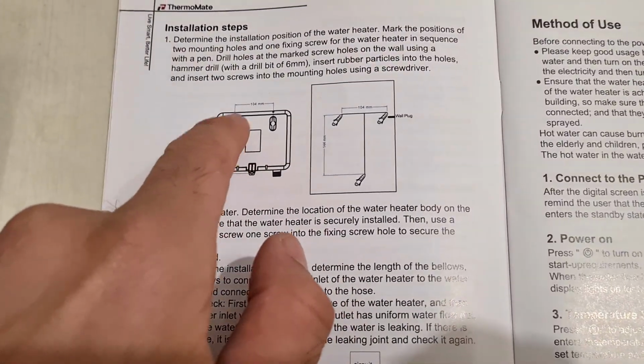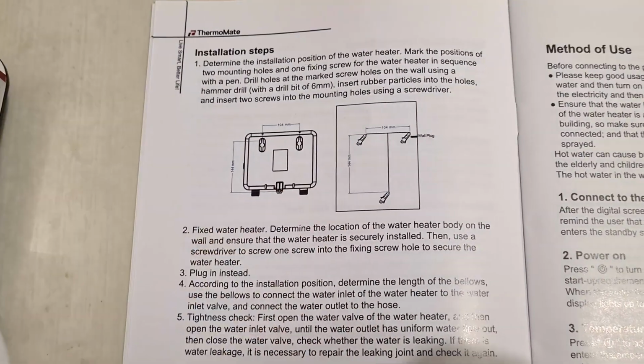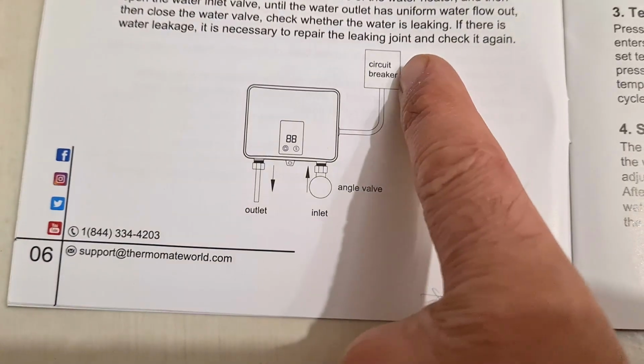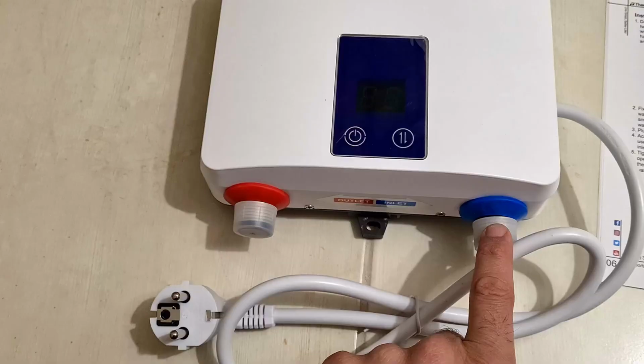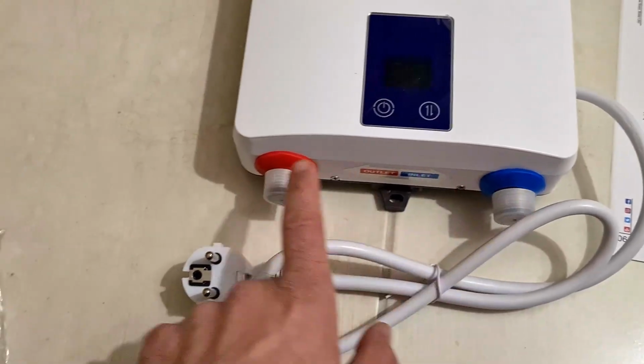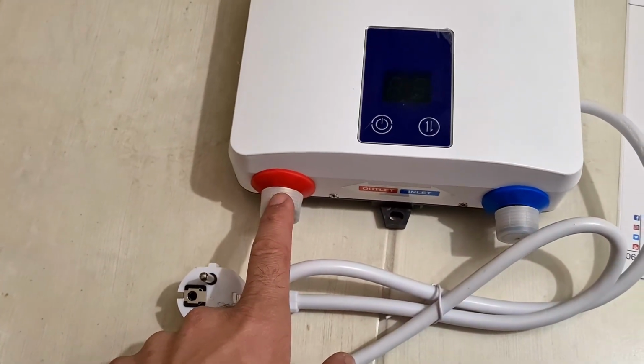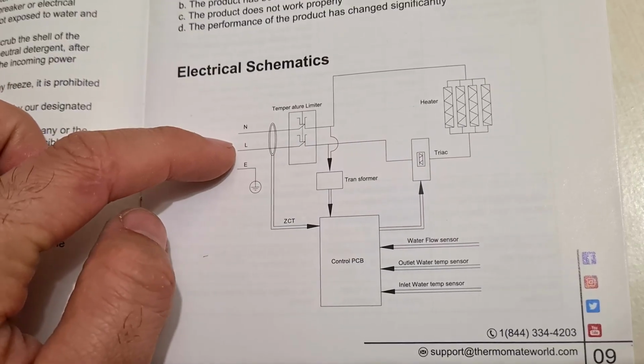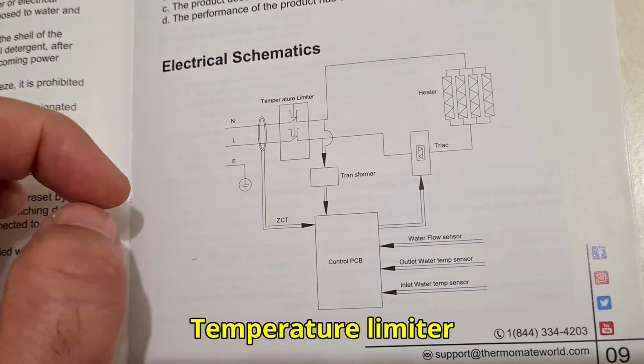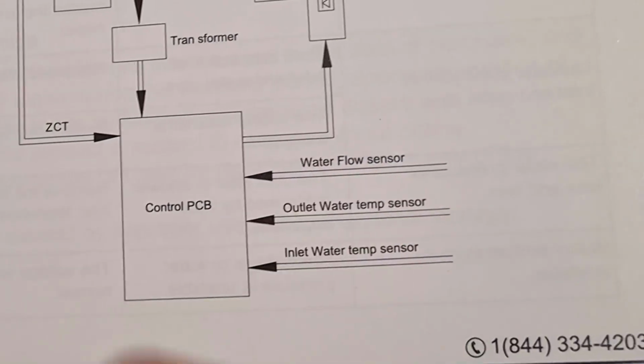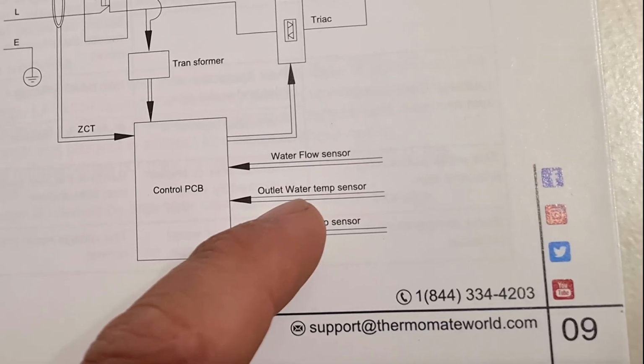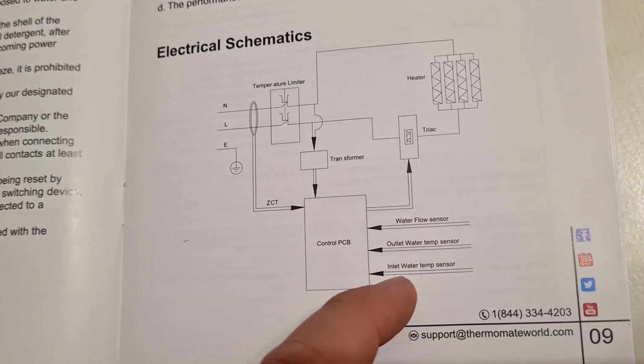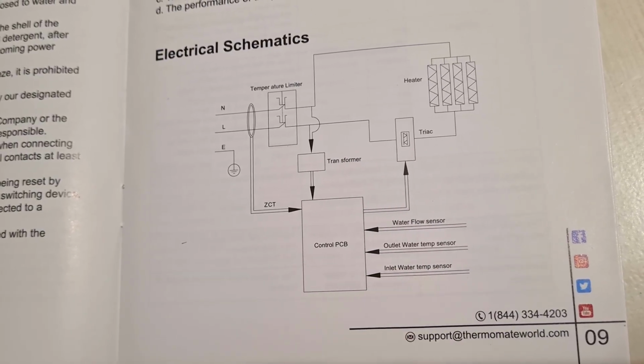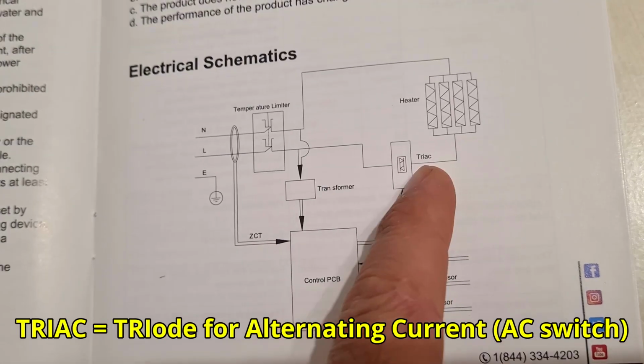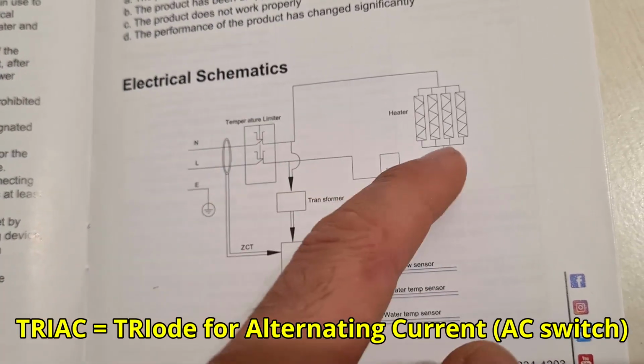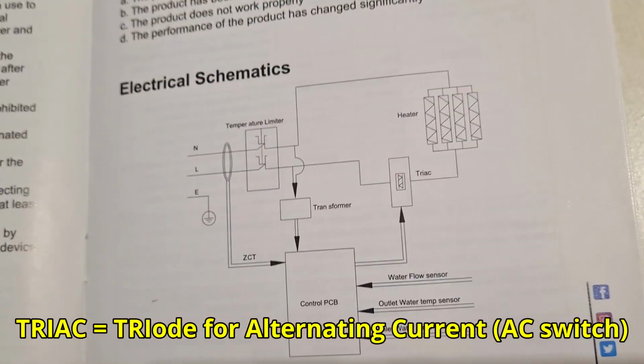That's the back side, 2+1 connectors. It should have a dedicated circuit breaker. One on the right is the cold water and the one on the left is the hot water. We have the neutral and the line, a temperature limiter. It has a water flow sensor, outlet water temperature sensor and inlet water temperature sensor. A triac, the switch which powers on the electricity for the heater element.